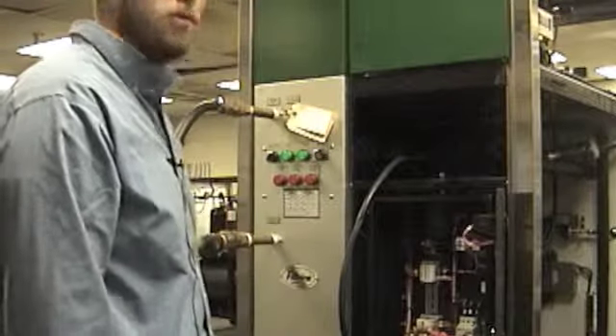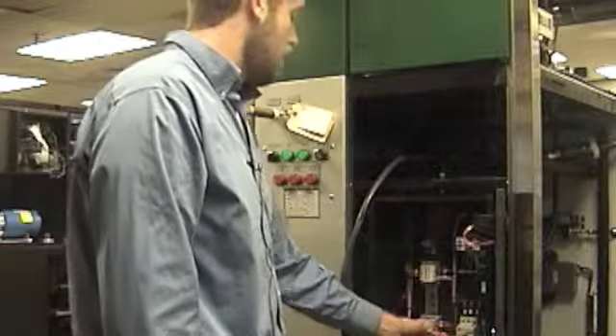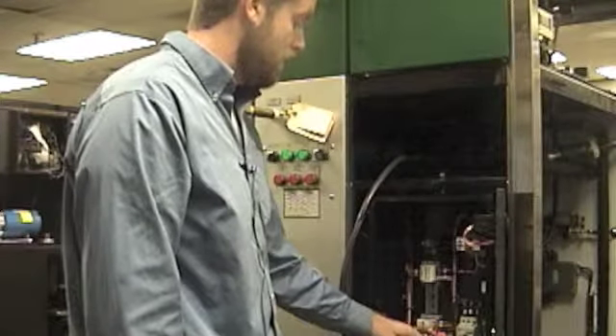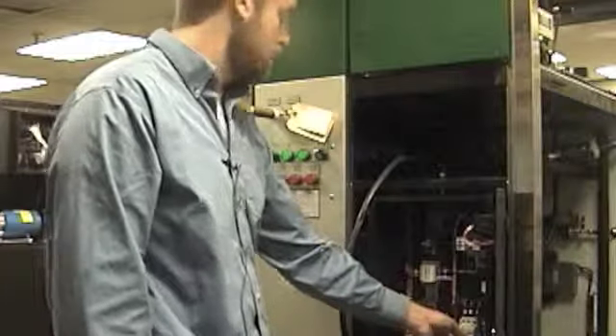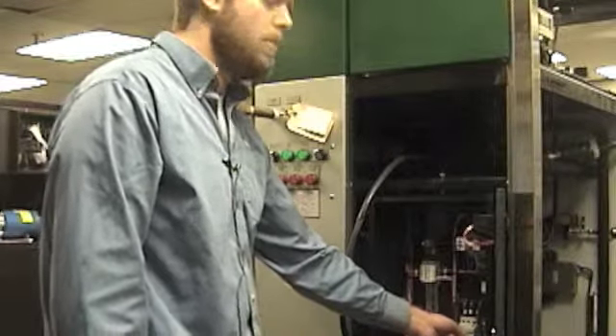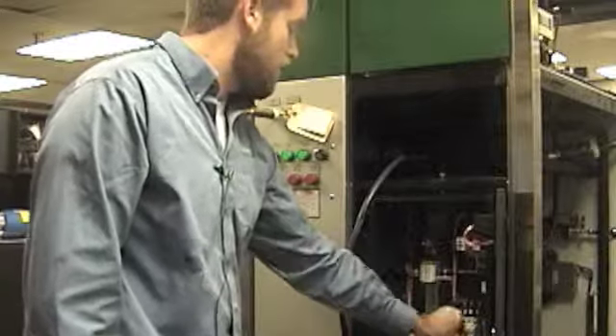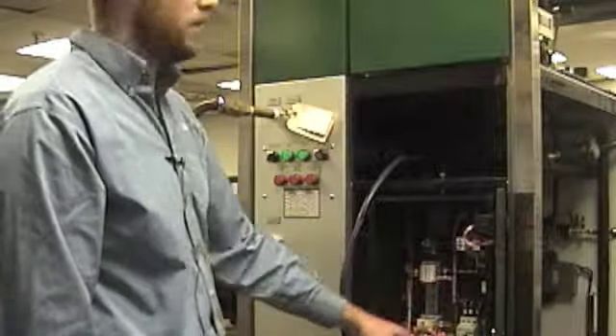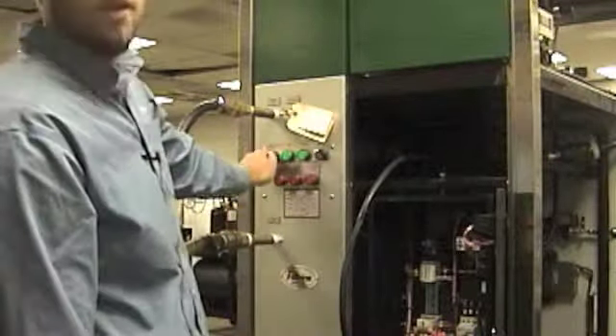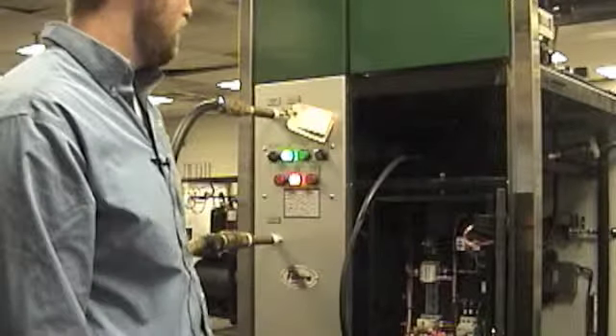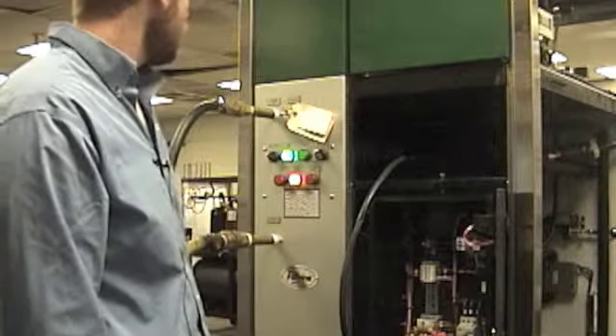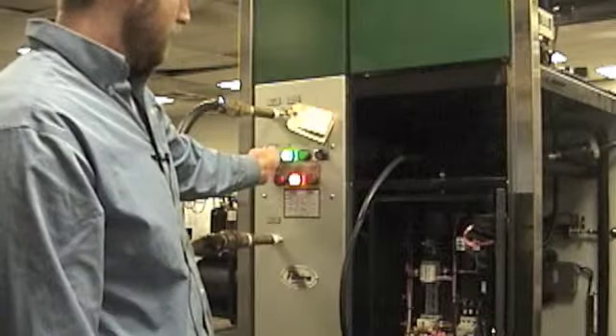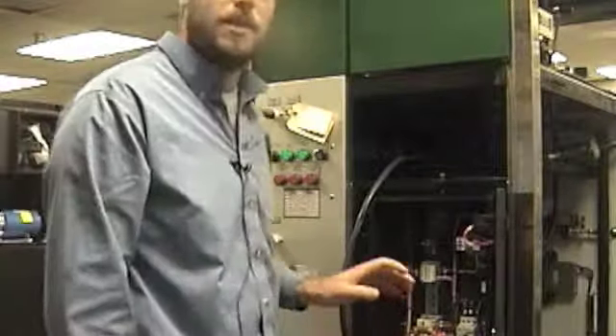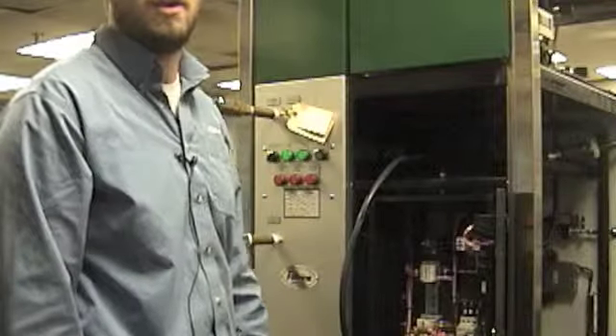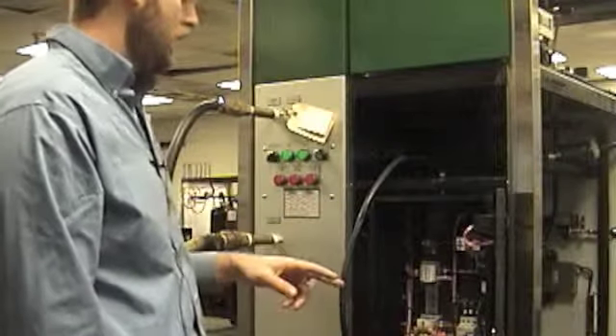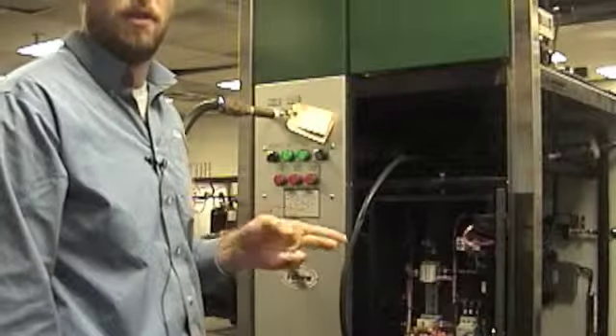So now that we have the unit filled, we're ready to start and run the pump. Obviously we haven't put the fuses in for the refrigeration system yet, as we haven't started that portion of the unit. But to start the pump, you want to flip this breaker on in the electrical box, the one designated for the pump, and then we can turn the 3-position switch to the manual side and get that running. What we want to do is actually check the rotation of the pump, make sure that on this unit, this 3-phase unit, that the legs aren't reversed.